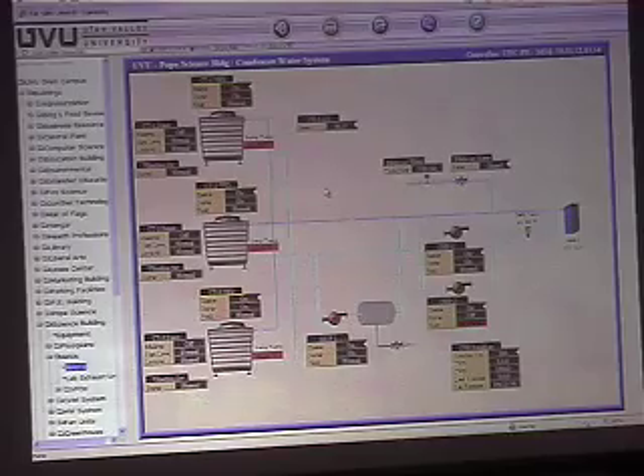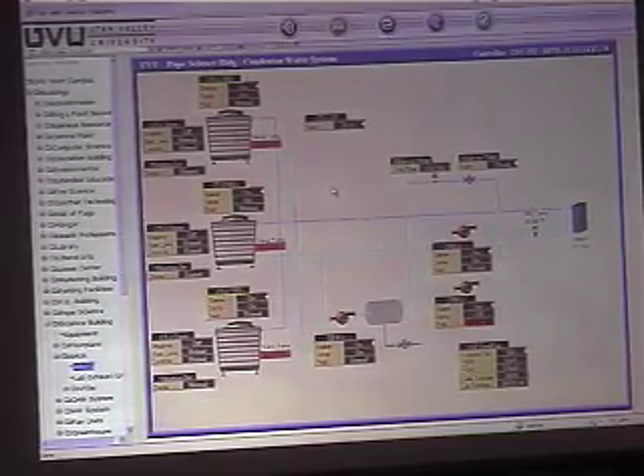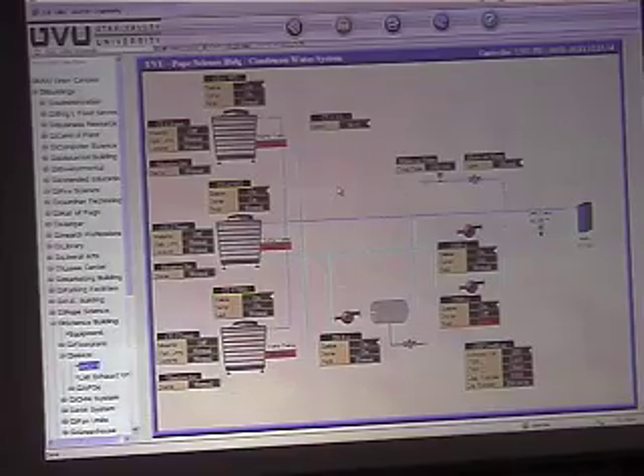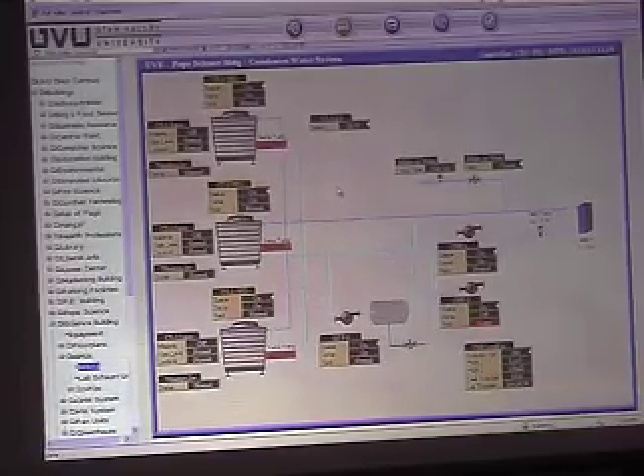You may have explained it while I stepped out, but are they staging the towers? No, the towers operate as one tower. Right. Okay. So yeah, they come on together and turn off together because they have a common sump. Okay. You said the first stage after economizing is the IDEC. Yeah, the indirect cooling. And then you go into evaporative after that. Yeah.